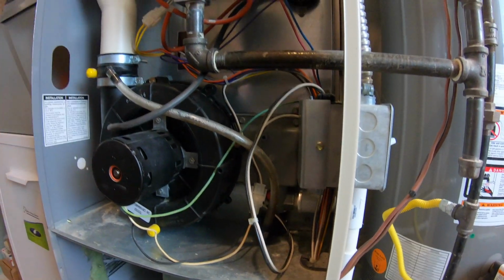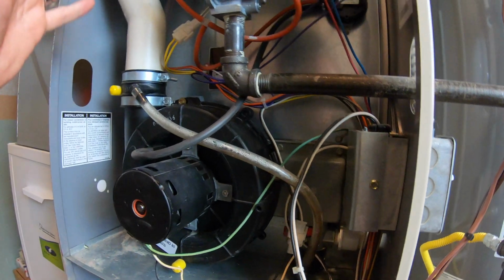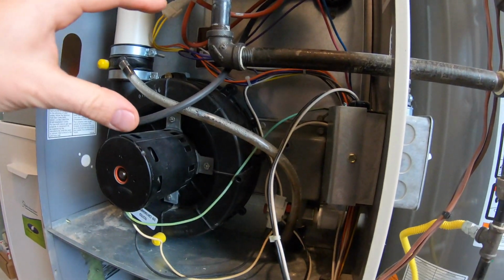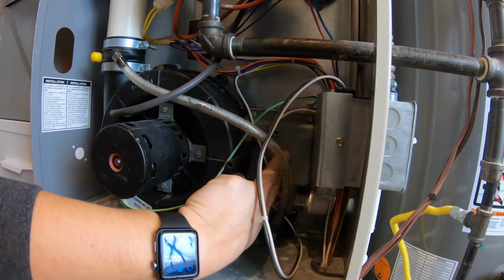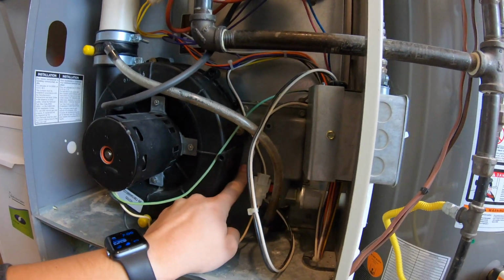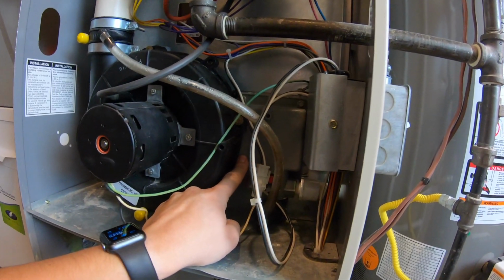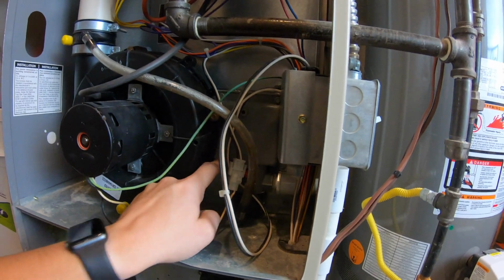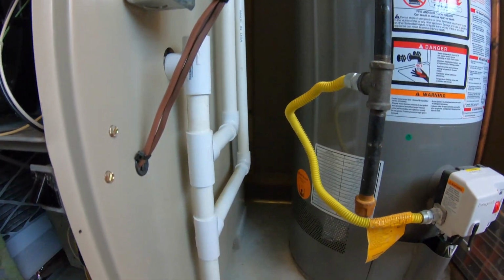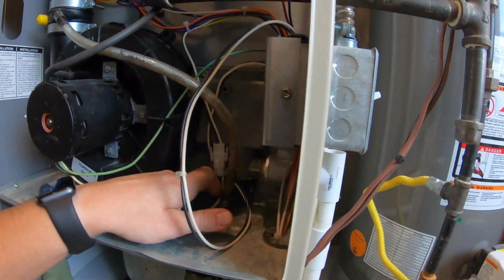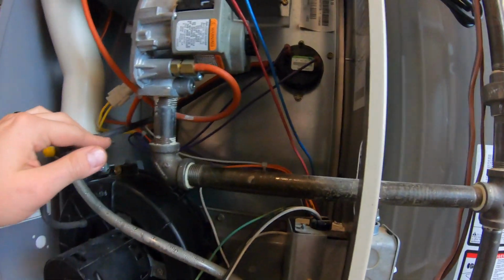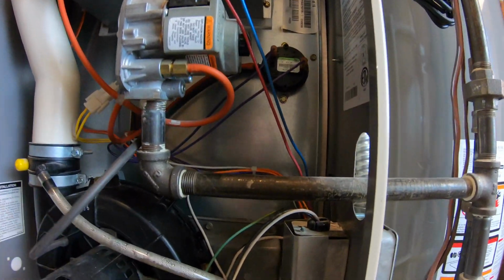On top of that, this is a condensing furnace, so it also condenses inside of the heat exchanger, which is this box right here. This secondary heat exchanger looks kind of like a radiator inside, and that also collects water and spits it out into this drain line. If for some reason that drain is backed up, it can cause your pressure switch to not close as well.